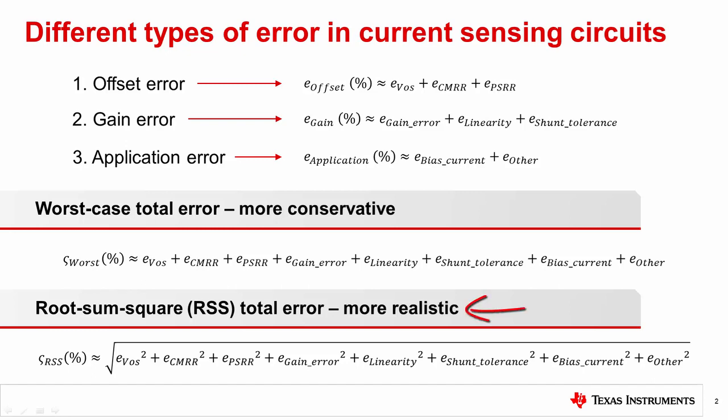A more realistic approximation of total error can be determined by using the root sum of the squares RSS method to combine the error types. To use this method, take the square of the maximum value for each error source, add them together, then take the square root of the result.